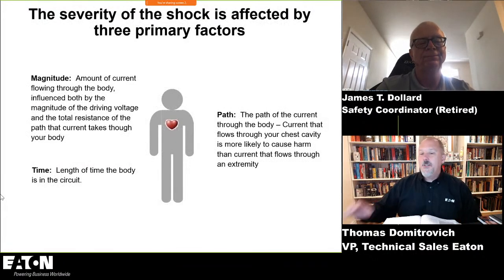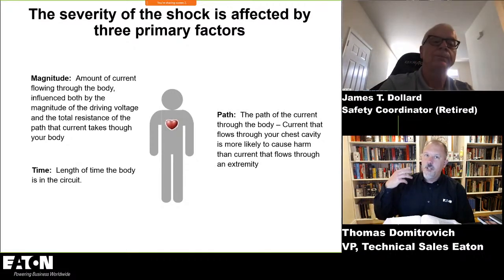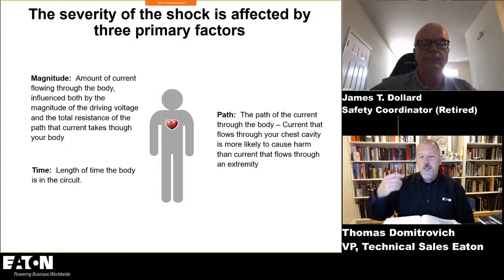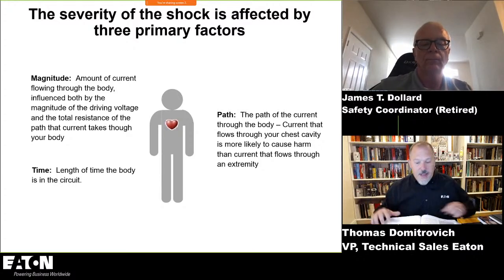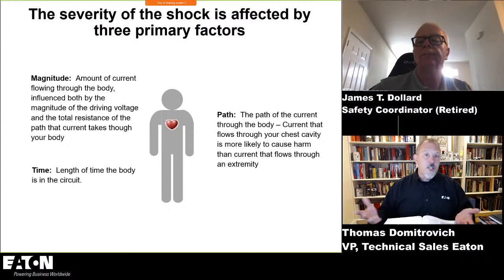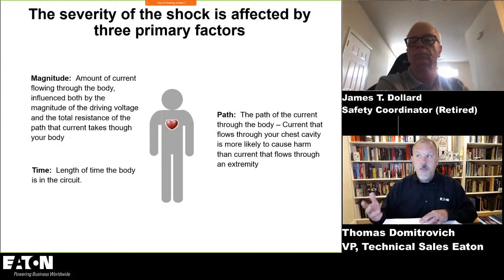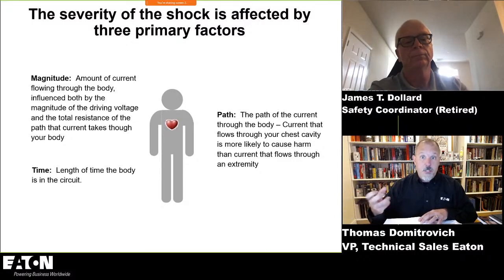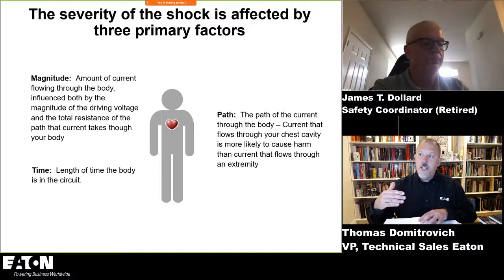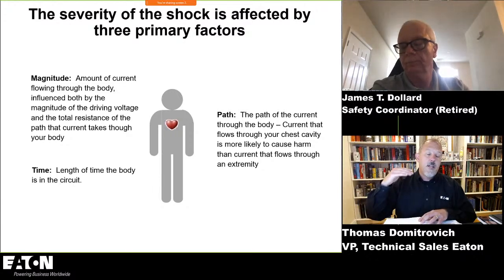Okay. So from our discussion on Monday, we were talking about from a shock perspective, the severity. You have to understand the path that the current takes through the body, the amount of current that passes through the body, and then the amount of time. And we talked a little bit on Monday about the fact that GFCIs don't limit the amount of current that flows through your body. A lot of people think that a 4 to 6 milliamp, no matter what circuit I'm hooked up on, I'm only going to see 4 to 6 milliamps. But in reality, you could see amps. But the overcurrent device is going to limit the amount of time that that current's permitted to flow through the body.